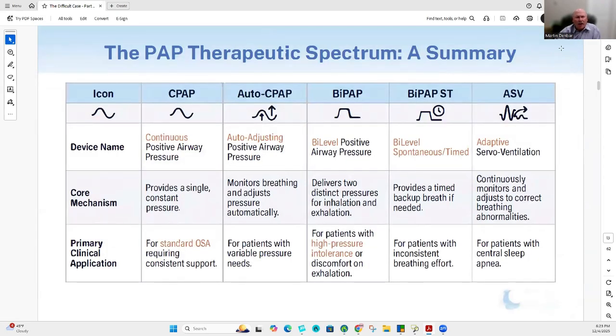So to summarize, CPAP is continuous, one pressure in, one pressure out. Auto is going to adjust to what you need. BiPAP is going to have a high pressure and then lower so you can exhale. With the ST, you're going to have a backup breath determined at the 16 channel, or the PSG, the overnight sleep study, to make sure that if they're seeing consistently 5 times a minute you're not breathing, they're going to put the timed breath there to make sure you're taken care of. And then the ASV is going to completely breathe for you.